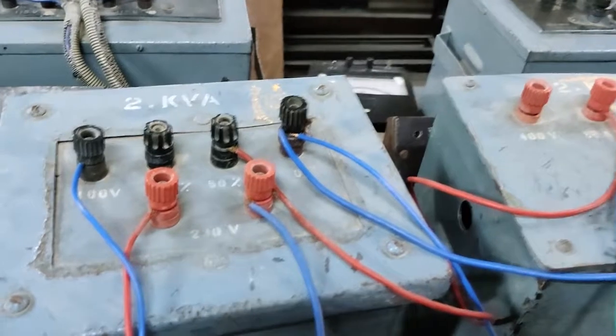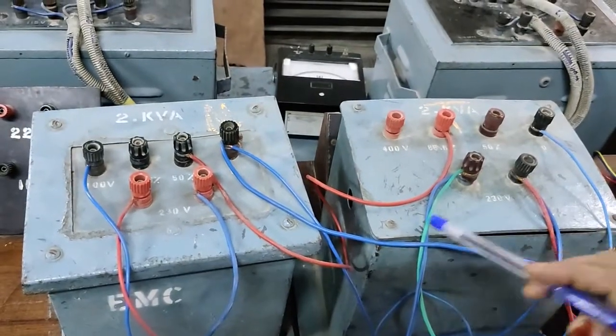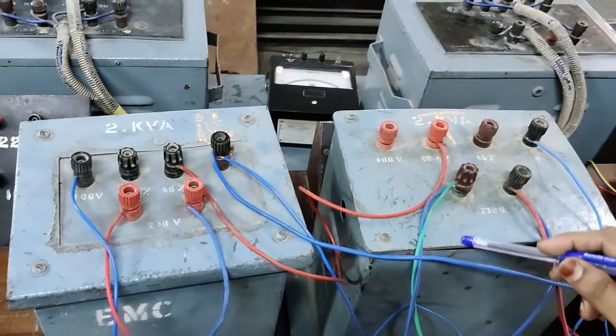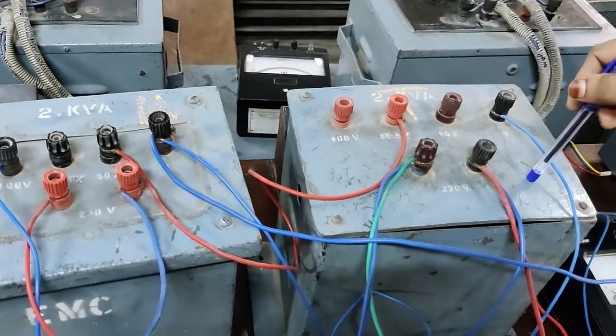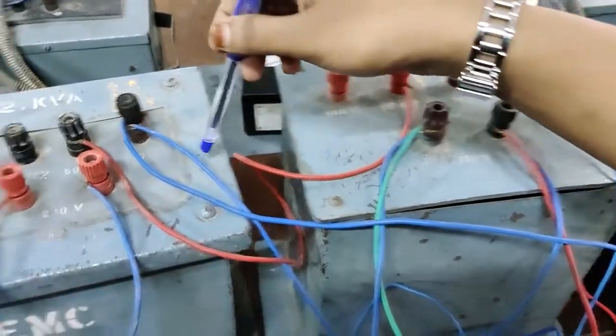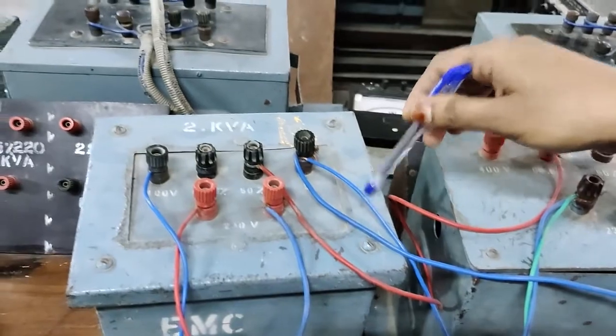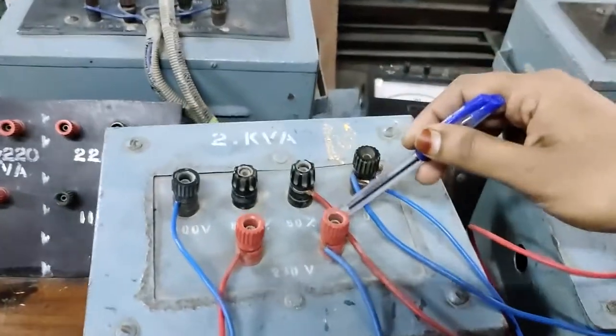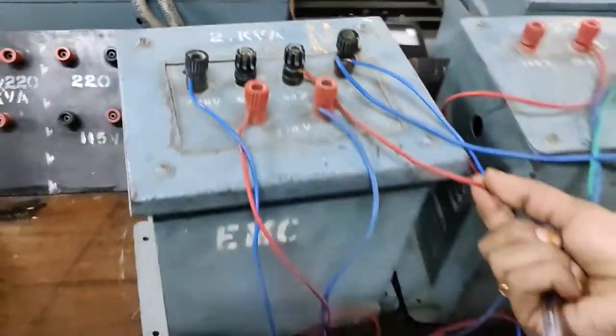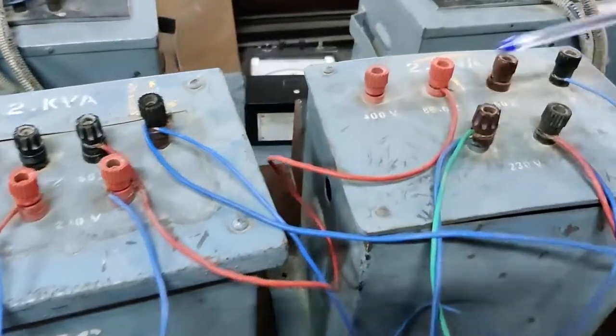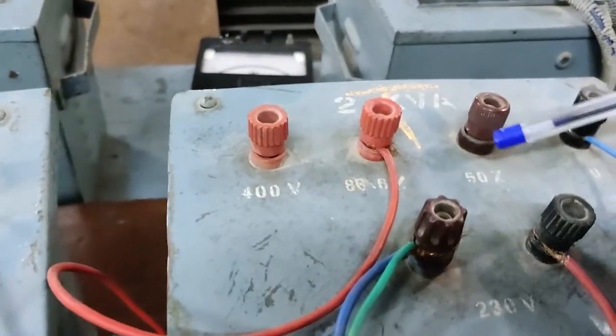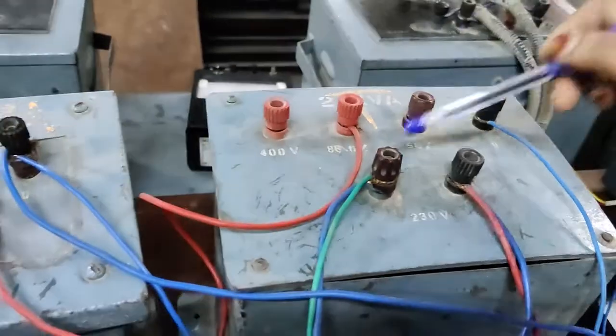These are the two single phase transformers. We are using it for the Scott connection, and you can see this is the teaser transformer and this one is the main transformer. And from the 50% tapping of the main transformer, it is connected to the 86.6% of the teaser transformer as per the circuit diagram.